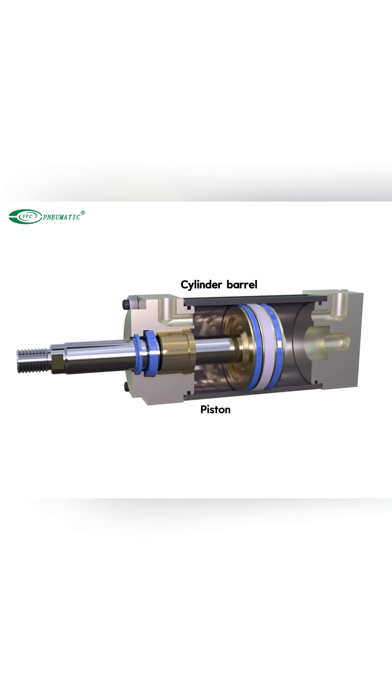After the cylinder is installed, run it 3 to 5 times at rated working pressure with no load. If there is no abnormality, then connect the load to run.